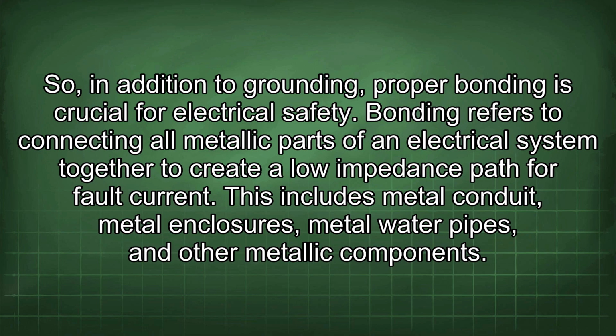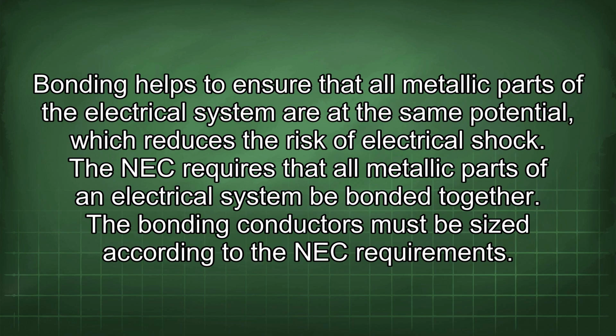Bonding refers to connecting all metallic parts of an electrical system together to create a low impedance path for fault current. This includes metal conduit, metal enclosures, metal water pipes, and other metallic components. Bonding helps to ensure that all metallic parts of the electrical system are at the same potential, which reduces the risk of electrical shock. The NEC requires that all metallic parts of an electrical system be bonded together.